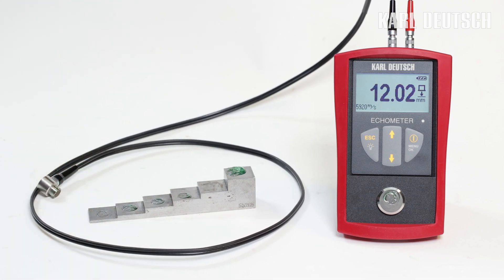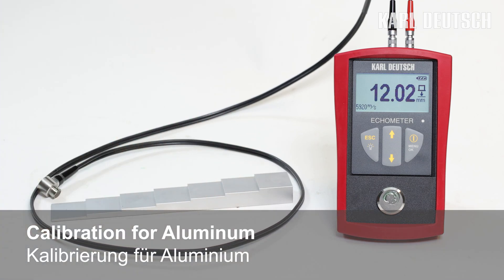It is also possible to measure components made of aluminum, plastic, or other materials. For this purpose, the appropriate sound velocity can simply be set on the device or measured on a calibration block.